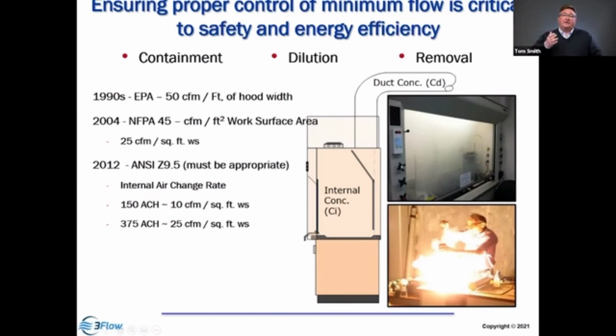So in the 90s, EPA came out with a standard that said 50 CFM per linear foot of hood width. Multiply the width of the hood by the velocity, and that will give you the flow. But in 2004, NFPA 45 said it should be based on the work surface, the depth, and the width. So if you had a 5 feet wide hood by 2 feet deep, that's 10 square feet. Multiply it by 25 CFM per square foot. Lo and behold, you get 250 CFM. But in 2010, NFPA 45 deferred to Z9.5. They no longer have this criteria.